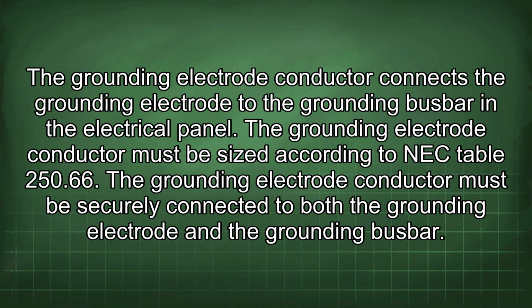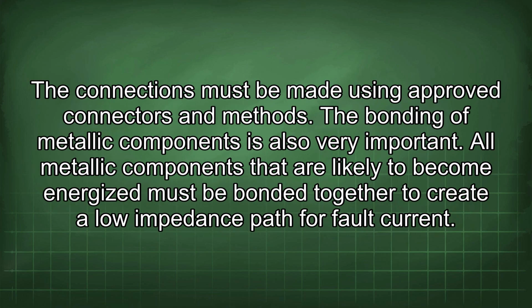The grounding electrode conductor connects the grounding electrode to the grounding busbar in the electrical panel. The grounding electrode conductor must be sized according to NEC Table 250.66. The grounding electrode conductor must be securely connected to both the grounding electrode and the grounding busbar. The connections must be made using approved connectors and methods.